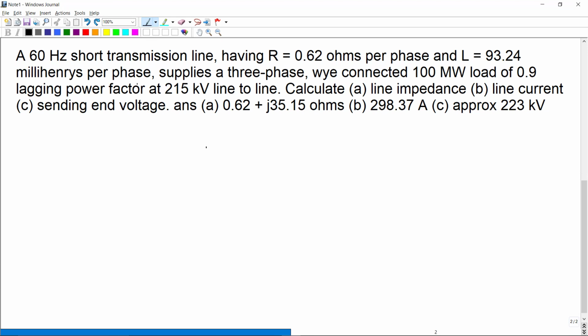Let's read the problem. A 60 Hz short transmission line has a resistance of 0.62 ohms per phase, and the inductance L is 93.24 millihenries per phase. It supplies a three-phase Y-connected 100 megawatt load at 0.9 lagging power factor, at 215 kilovolts line to line. Calculate three quantities: the line impedance, the line current, and the sending end voltage.